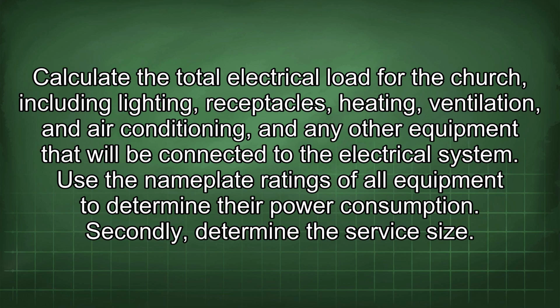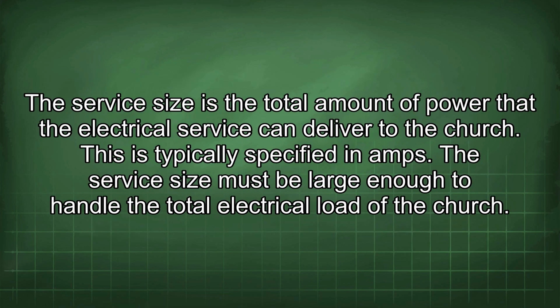Secondly, determine the service size. The service size is the total amount of power that the electrical service can deliver to the church. This is typically specified in amps. The service size must be large enough to handle the total electrical load of the church.